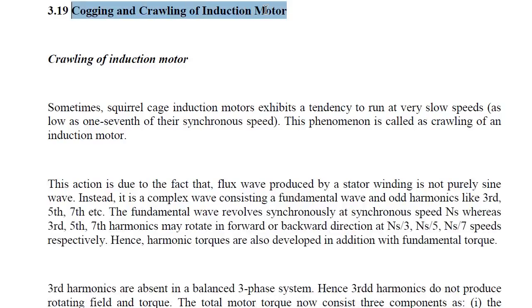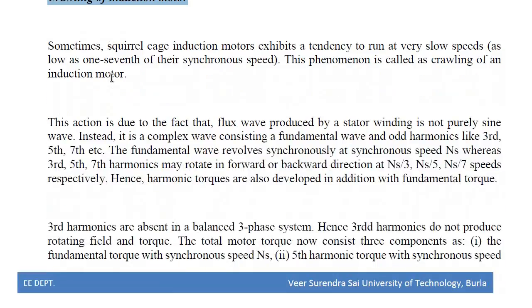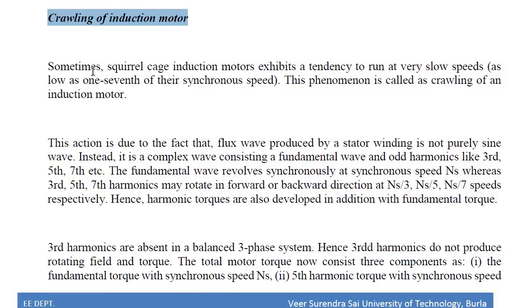Now we discuss cogging and crawling effects in the induction motor. First, the crawling effect: sometimes the squirrel cage induction motor exhibits a tendency to run at a very slow speed, as low as 1/7th of its synchronous speed NS. This phenomenon is called crawling of an induction motor — the motor runs at a very low speed instead of accelerating to its normal synchronous speed.